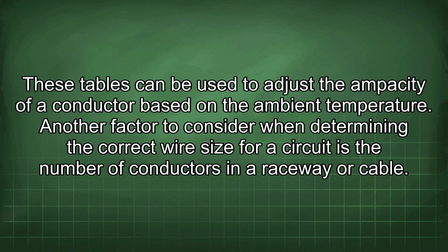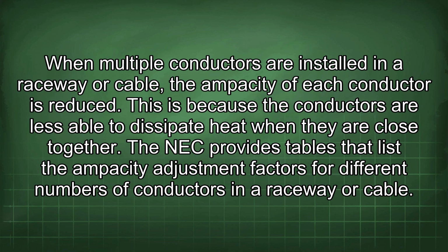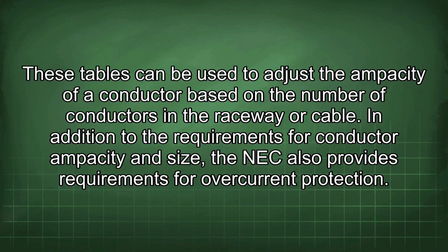Another factor to consider when determining the correct wire size for a circuit is the number of conductors in a raceway or cable. When multiple conductors are installed in a raceway or cable, the ampacity of each conductor is reduced. This is because the conductors are less able to dissipate heat when they are close together. The NEC provides tables that list the ampacity adjustment factors for different numbers of conductors in a raceway or cable. These tables can be used to adjust the ampacity of a conductor based on the number of conductors in the raceway or cable.